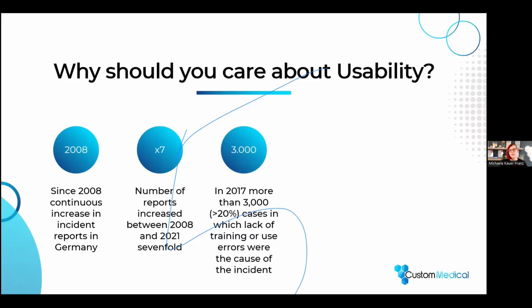In 2017, there was a quite detailed analysis of the incidents, and more than 20% of the then reported incidents, so more than 3,000 cases, were related to a lack of training or use errors as a cause of the incident. So more than 20% were usability related. This is one of the causes why the importance of usability is increasing, especially because the number of lay user products and the number of digital products in the medical sector is increasing also.